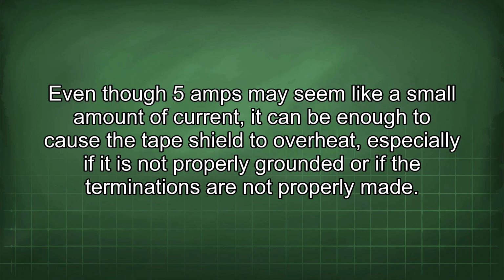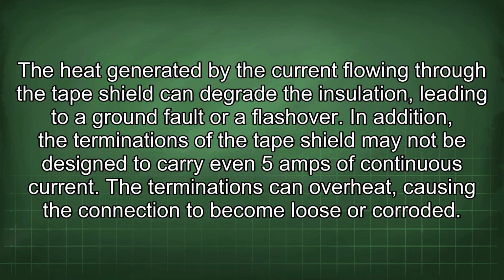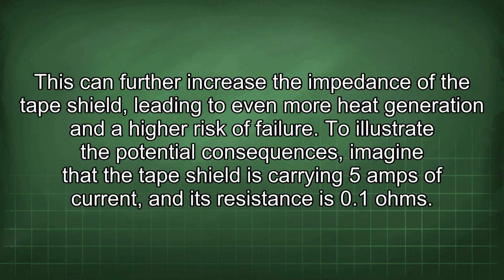Even though 5 amps may seem like a small amount of current, it can be enough to cause the tape shield to overheat, especially if it is not properly grounded or if the terminations are not properly made. The heat generated by the current flowing through the tape shield can degrade the insulation, leading to a ground fault or a flashover. In addition, the terminations of the tape shield may not be designed to carry even 5 amps of continuous current. The terminations can overheat, causing the connection to become loose or corroded. This can further increase the impedance of the tape shield, leading to even more heat generation and a higher risk of failure.